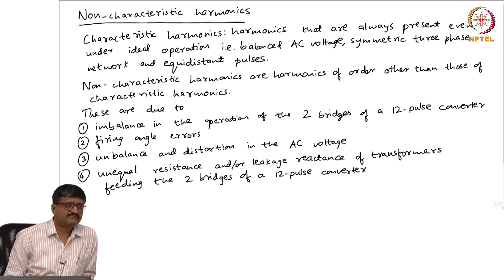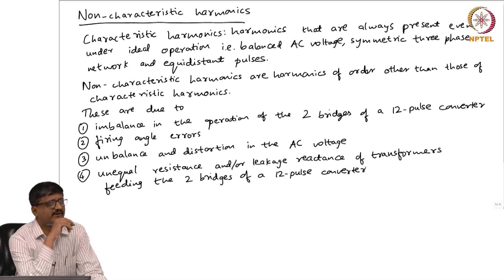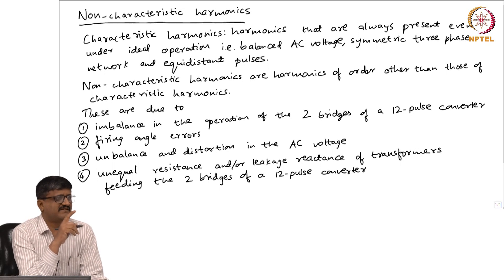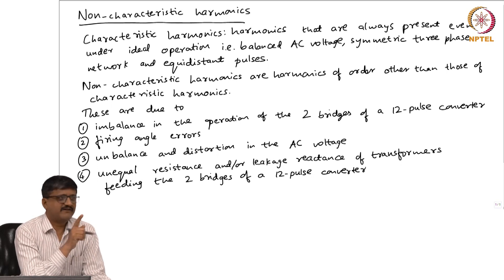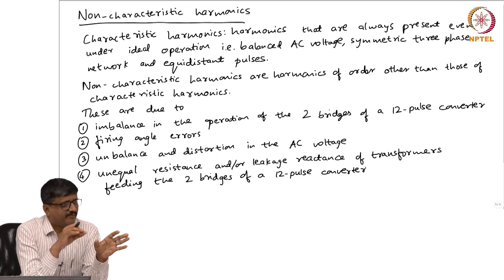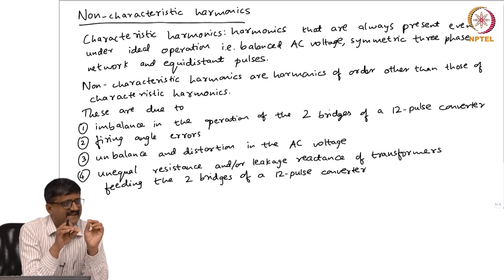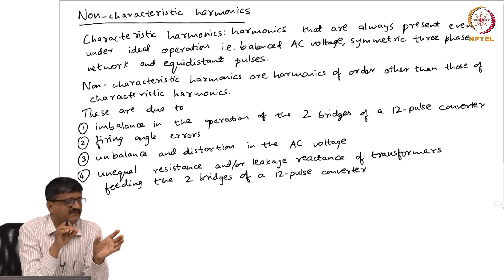Another question concerns the assumption of unequal resistance and leakage reactance. The assumption made earlier was that the resistance and leakage reactance are the same for both transformers. If they are not the same, there will be no perfect cancellation. However, the point is that these resistances and leakage reactances are small. So although there will not be complete elimination, there will be a drastic reduction in all those harmonics which are not supposed to be there ideally.